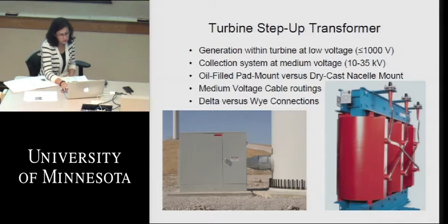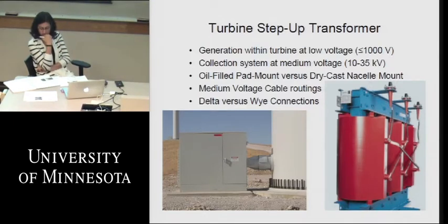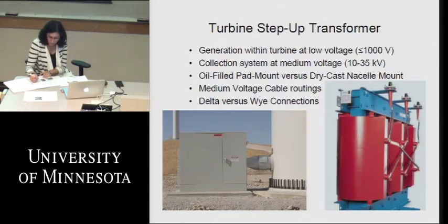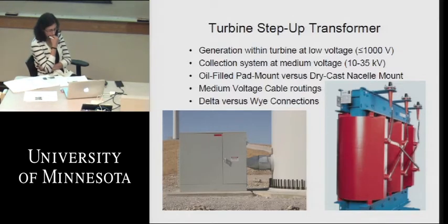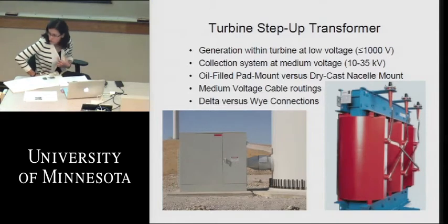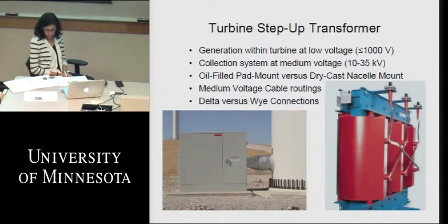But we've got to step up to the collection system voltage, which I show here. It could be anywhere from 10 to 35 kV. Generally the highest we run is 34.5 kV. We call it 35 kV, but it's actually 34.5. That's because coming out of the wind turbine, we use underground construction, and the standard off-the-shelf components from manufacturers for normal distribution systems only go up to 34.5 kV. That way we don't need unique components built for the wind industry, and in a pinch we can just go down to our electrical distributor and get what we need. So we try to keep it within the standard voltages that distribution uses for routing power out to your house or within your city.